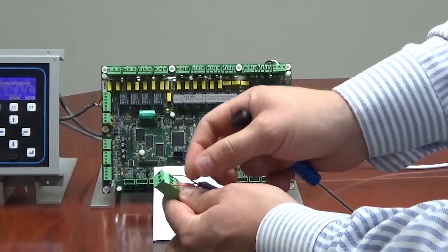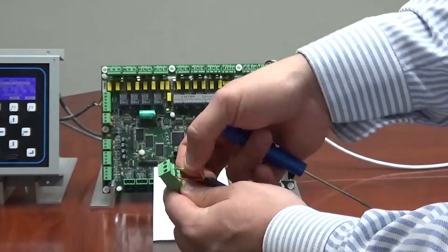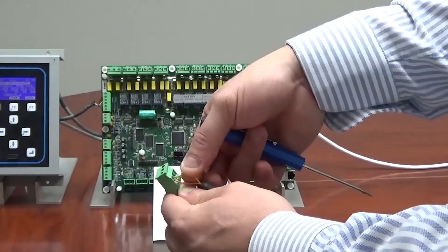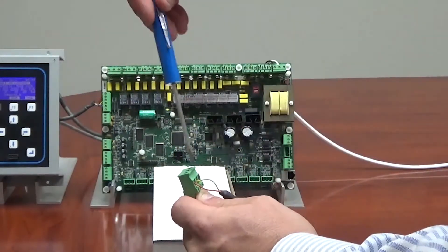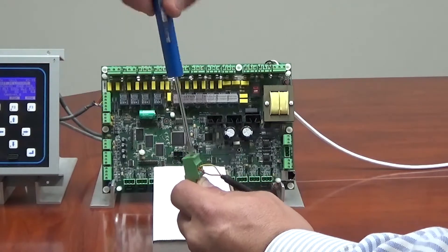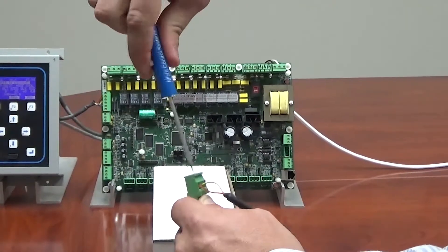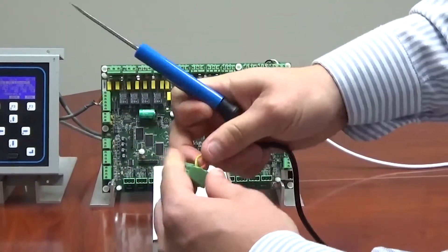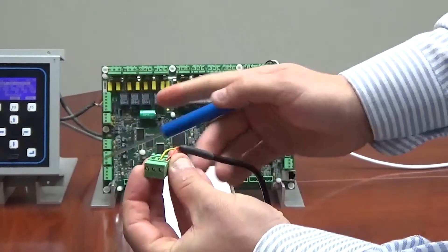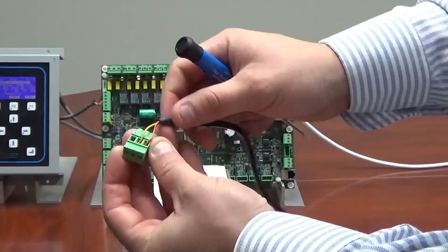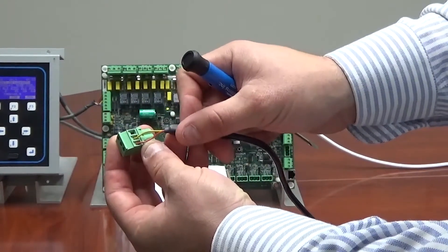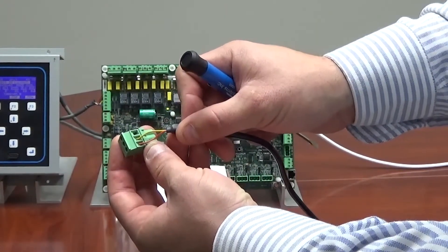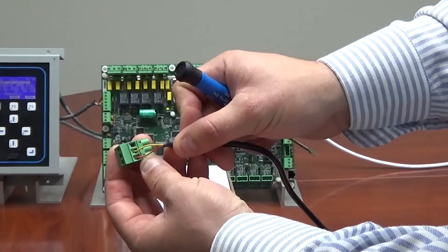Then we're going to wire the yellow to the negative terminal, and that's going to be in the middle of the three position block. Be sure after you get these tightened down that you are only on the conductor in the terminal and that you're not pinching any insulation, as that could cause communication problems.